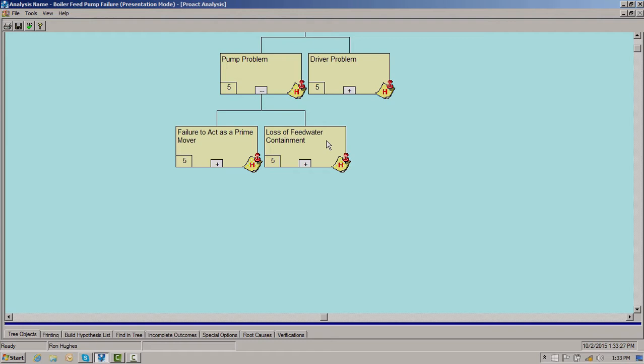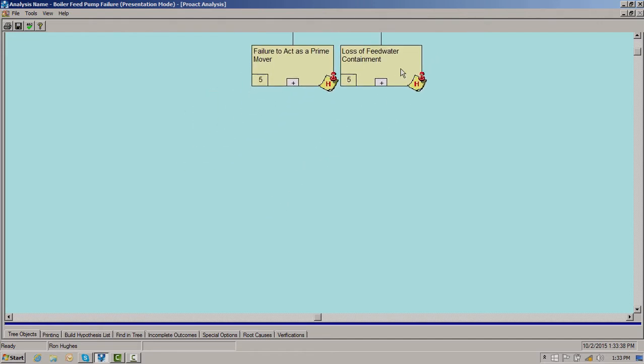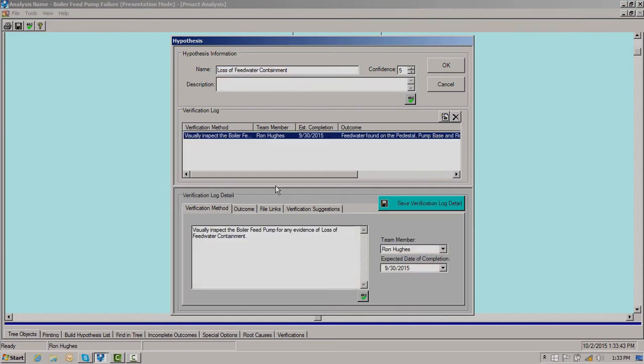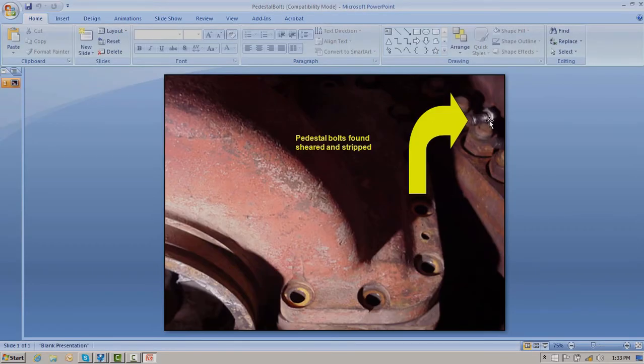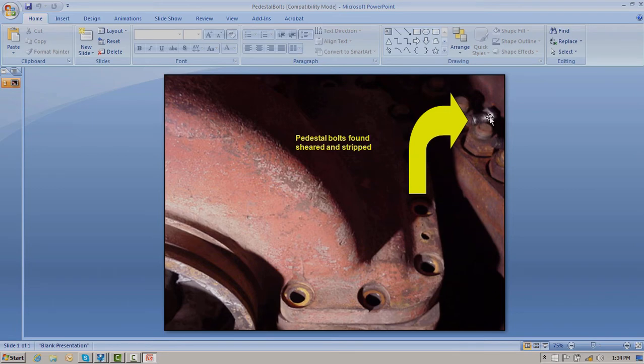For loss of feed water containment, you look on the floor, on the pedestal, on the foundation — and we see feed water. Obviously we have loss of feed water containment. Looking here, you can see one of the pedestal bolts. Now these pedestal bolts were not removed by the maintenance staff — they were physically taken out by the failure itself. This indicates that the failure is pretty powerful and something is happening inside this pump.